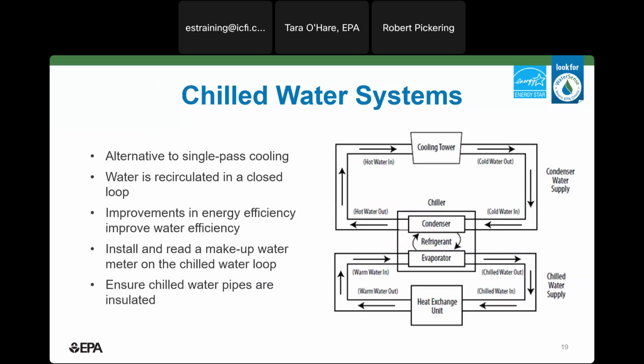So fortunately, most facilities that have substantial cooling loads use recirculated chilled water systems. Chilled water systems typically have several key components. They have a heat exchange unit. These are supplied with chilled water that is providing either space cooling or some other equipment cooling. This is where the heat load comes from. The chilled water takes that heat load and directs it back to the chiller. Typically, a chilled water loop is a full closed loop, and therefore you should be seeing very little water loss or consumption in this chilled water loop. It's good practice to have makeup water meters on the chilled water loop so that if you see any consumption or continuous makeup, you can identify that you likely have a leak and you can get it resolved.